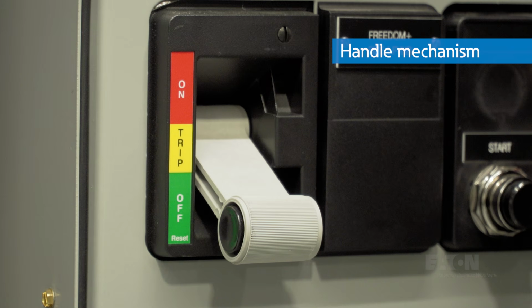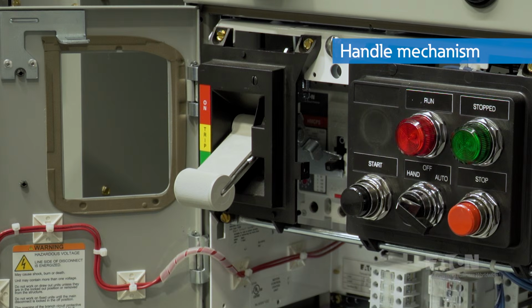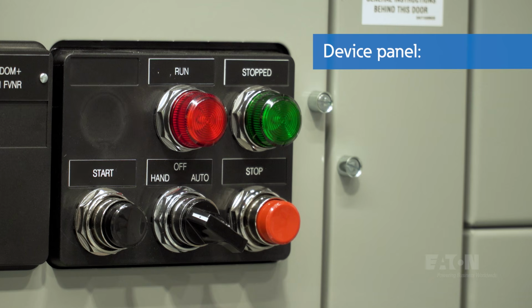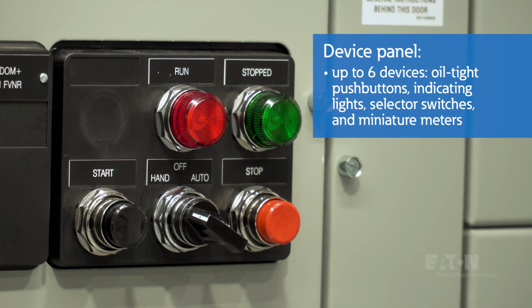The handle mechanism is designed to provide a high mechanical leverage so that little effort is required to operate the device. The device has 4 positions: on, off, tripped, and reset. Only circuit breaker types have tripped and reset positions. It is securely mounted to the front of the unit and mechanically connected to the breaker or fusible switch, eliminating alignment problems. The device panel can accommodate up to 6 30mm pilot devices such as oil-tight push buttons, indicating lights, selector switches, and miniature meters.